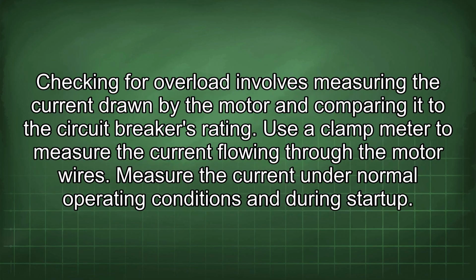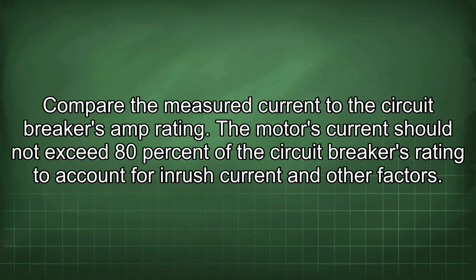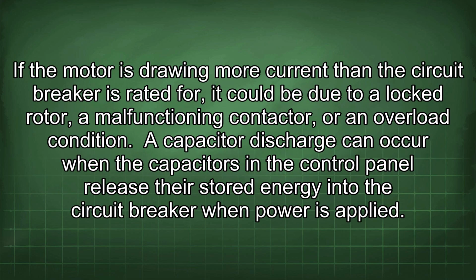Checking for overload involves measuring the current drawn by the motor and comparing it to the circuit breaker's rating. Use a clamp meter to measure the current flowing through the motor wires. Measure the current under normal operating conditions and during startup. Compare the measured current to the circuit breaker's amp rating. The motor's current should not exceed 80% of the circuit breaker's rating to account for inrush current and other factors. If the motor is drawing more current than the circuit breaker is rated for, it could be due to a locked rotor, a malfunctioning contactor, or an overload condition.